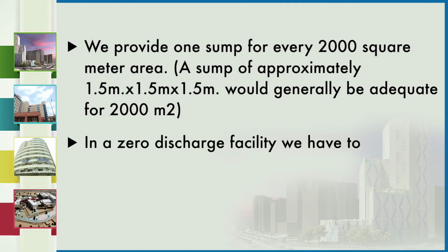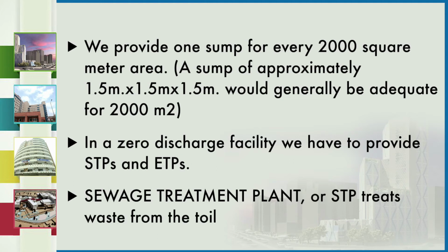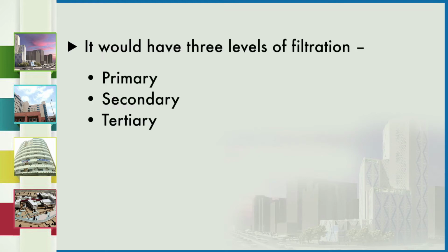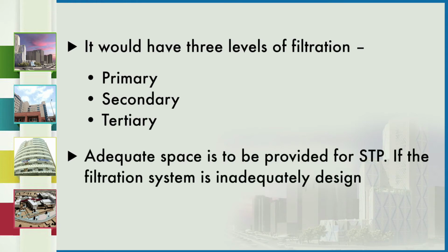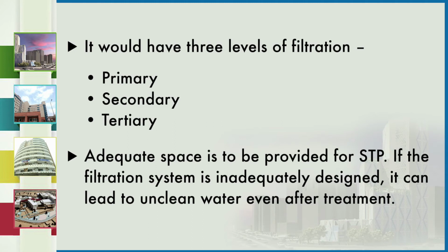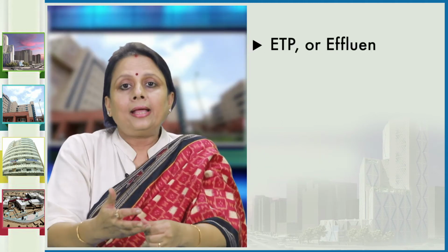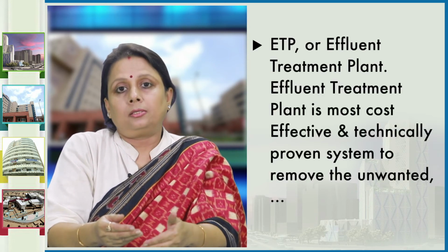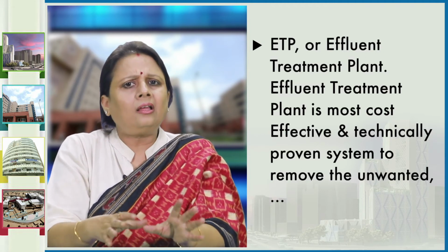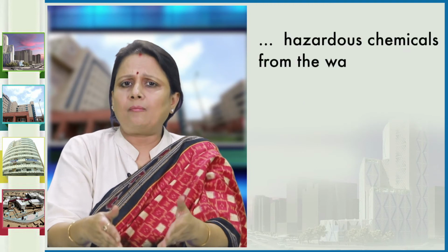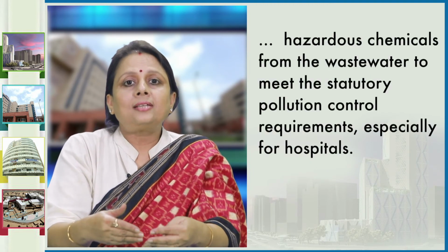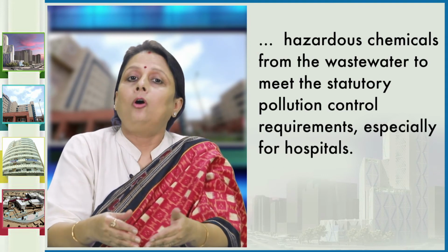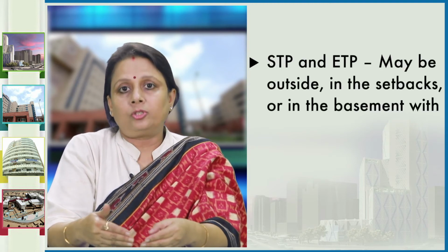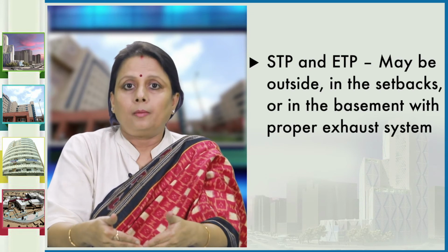In a zero discharge facility, we have to provide STPs and ETPs within the site. STP is sewage treatment plant. It treats the water from the toilets and kitchen. It would have 3 levels of filtration: primary, secondary and tertiary. So adequate space has to be provided for STP. If the filtration system is inadequately designed, it can lead to unclean water even after treatment. Next is ETP or effluent treatment plant, which is a most cost-effective and technically proven system to remove the unwanted hazardous chemicals from the wastewater to meet the statutory pollution control requirements, especially for hospitals. The STP and ETP may be outside in the setbacks or in the basement, but with proper exhaust system.